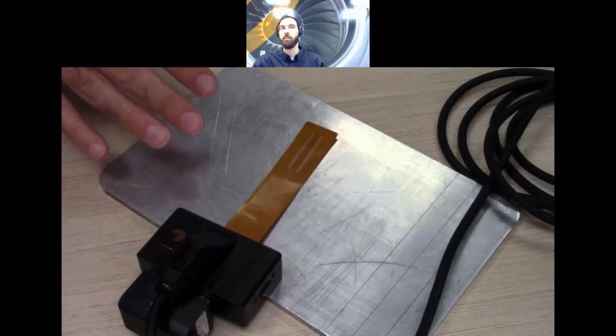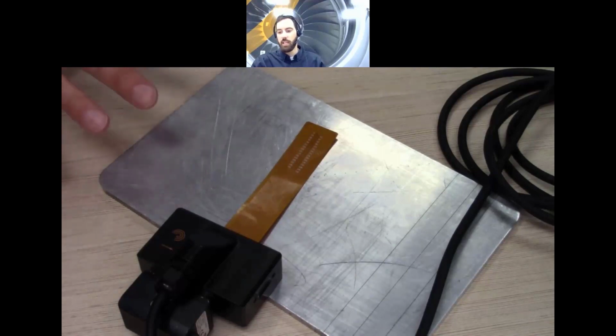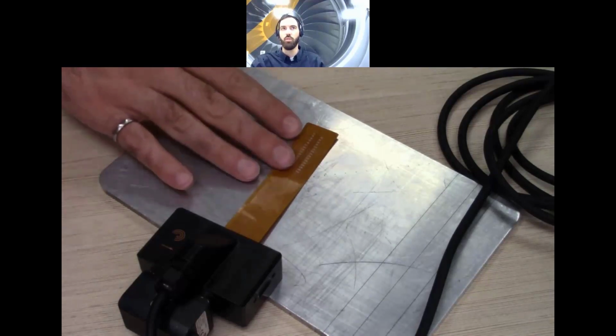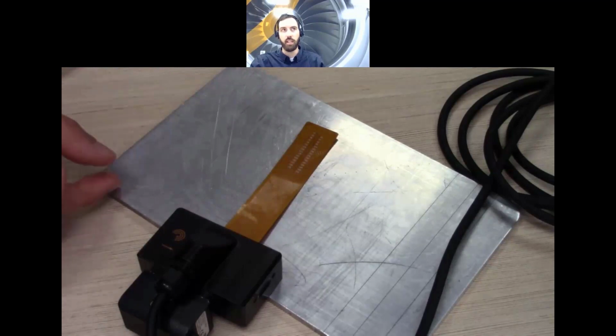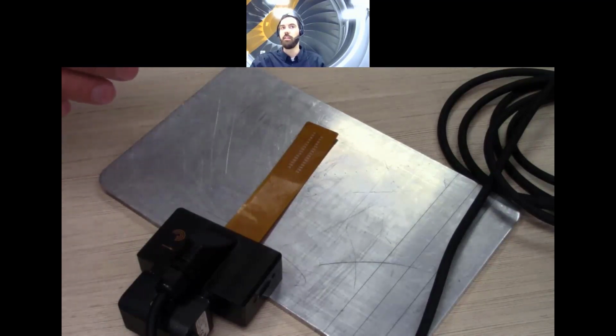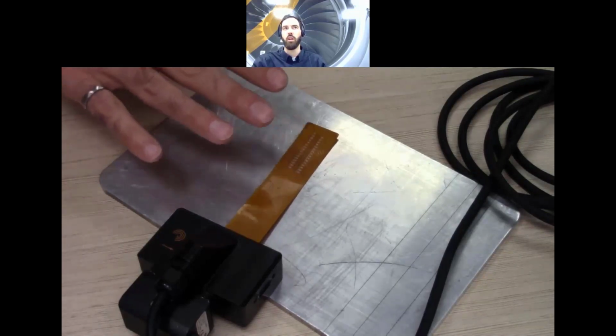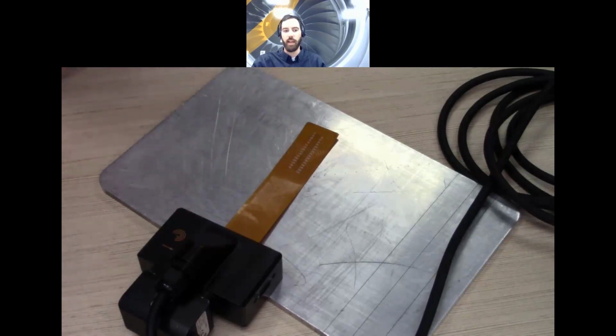However, it is very limited in terms of penetration. This should not be used to penetrate a thick layer of stainless steel or a thick layer of aluminum and detect flaws on the other side. We have probes specifically for this. We have iFlex probes that go low frequency that are great for that. The point of the PFlex here is really for surface breaking defects at high frequency.